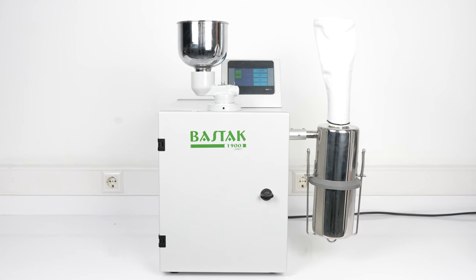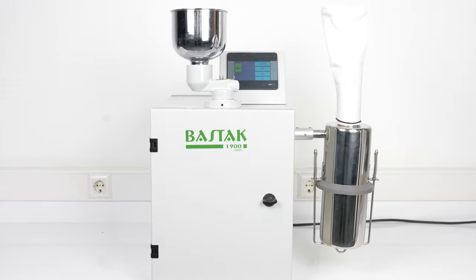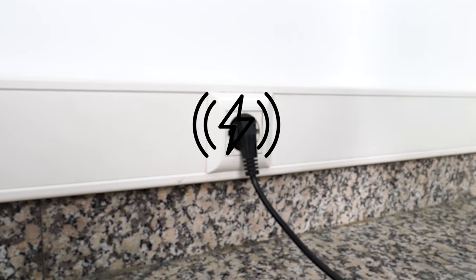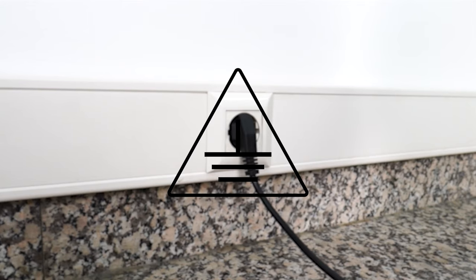The BASTAK 1900 Smart Model Hammer Mill Device is placed on a flat and solid surface. The device is used at 220 volt and 50 hertz grounded mains voltage. The grounding of the laboratory where the device will be installed is measured. The grounding value should be less than or equal to 5 ohms; if not, the grounding line is drawn again.